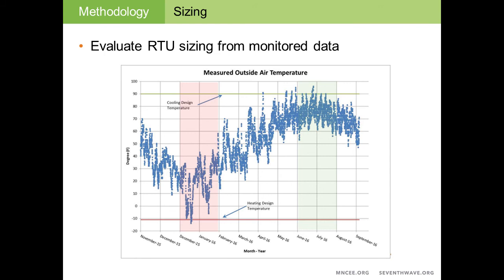To give you an indication of whether we had design temperature or not, this is a plot of outdoor air temperature that was experienced during the monitoring period. You can see during the heating period, that's the shaded red area, we did experience a few times in the interval data that we achieved design temperatures, and then further to the right, we had a number of days where we had the cooling design temperature, which is depicted by the shaded green area.